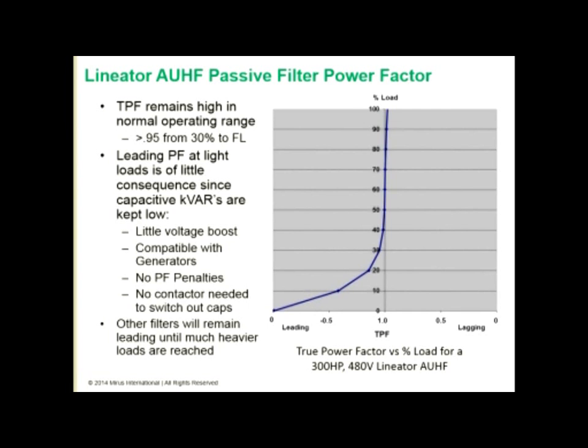So the previous curve showed the capacitive reactive power. Well, the capacitive reactive power in combination with the inductive reactive power is going to result in the power factor as measured at the input to the filter. So here we show the total power factor on the x-axis, again leading on the left from unity to 0, lagging on the right from unity to 0. And we can see that for our filter, from loading 30% and above, we are very close to unity and above 0.95 over that entire range.